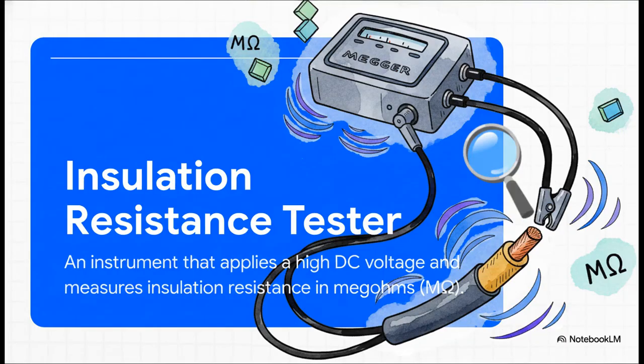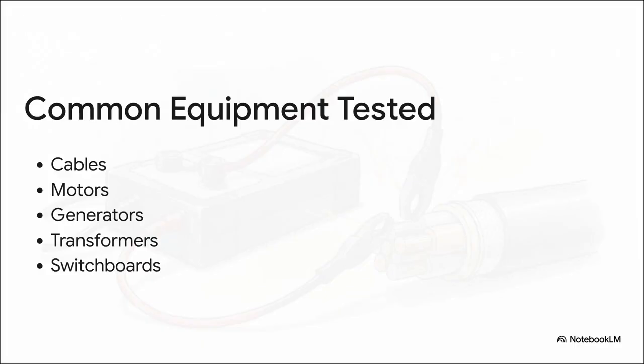An insulation resistance tester, which pretty much everyone just calls a Megger, that's a brand name that totally stuck, is designed to do one job, and do it incredibly well. It checks the health of electrical insulation. And it does this by sending a very high DC voltage through it and then measuring the resistance in millions of ohms, or what we call megaohms. And we're not just talking about small stuff here. We are talking about the heavy hitters, the critical cables running through an entire facility, the windings inside powerful motors, shipboard generators, transformers, and the giant switchboards that control everything. This thing is an absolutely essential tool for preventative maintenance.